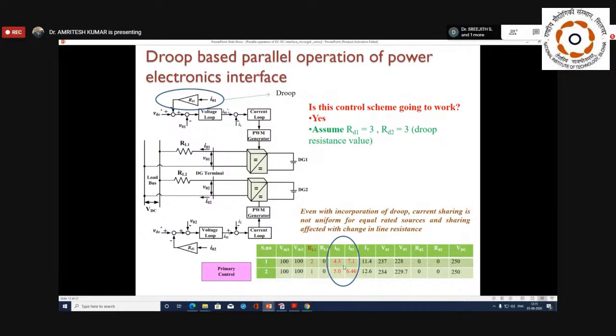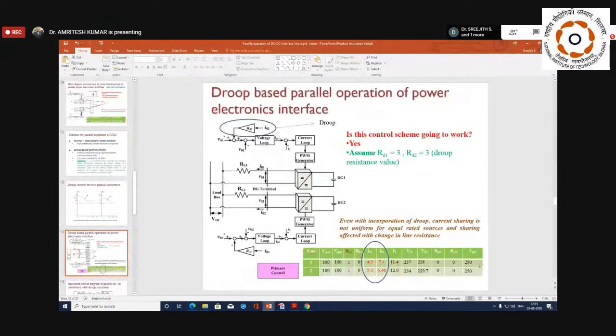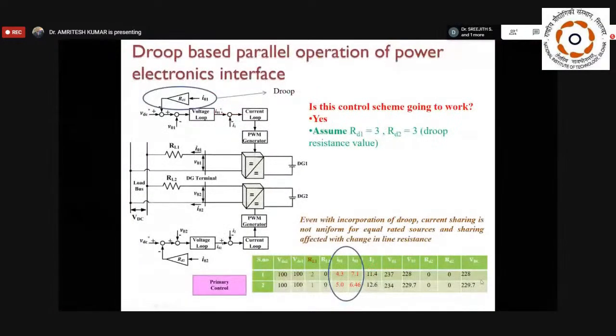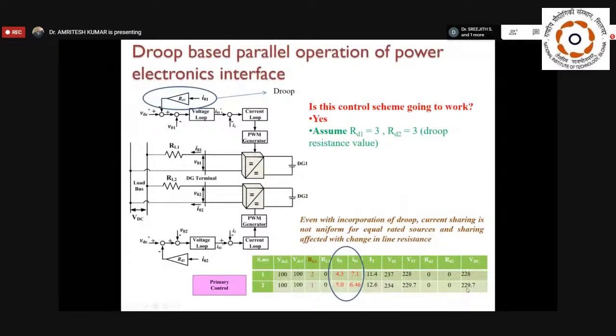Okay, but again with smaller droop you can see that even if they are of equal rated condition, there's a difference in the current sharing. Moreover, there's a high decrease. One second, this value should actually be 228, and edit it, otherwise we will create confusion. So this should actually be 228 and 229.7.